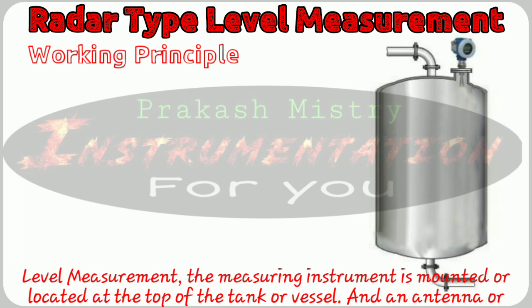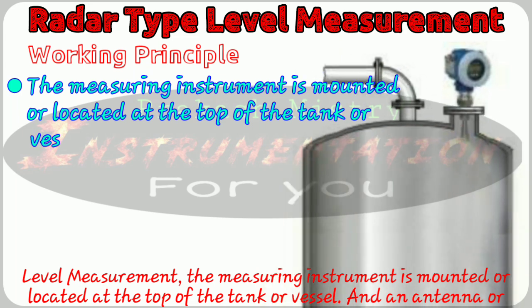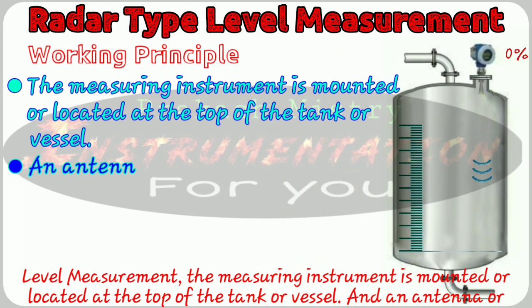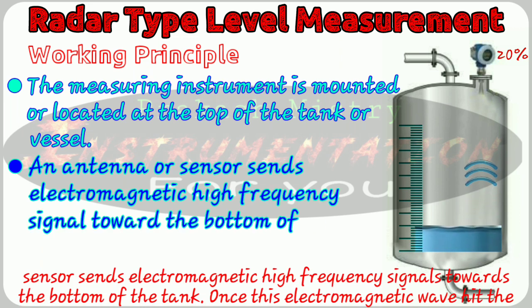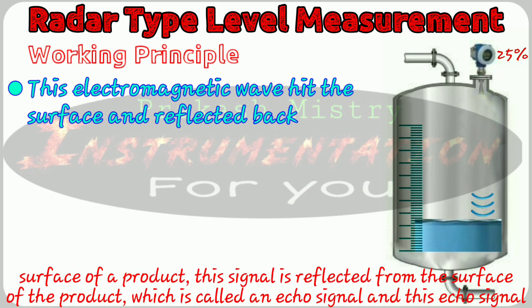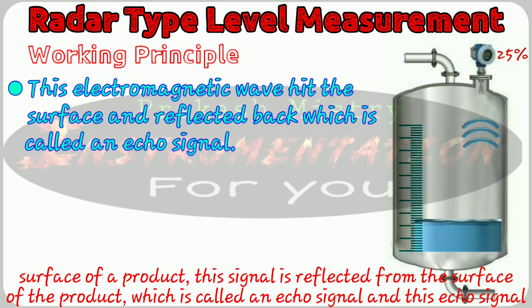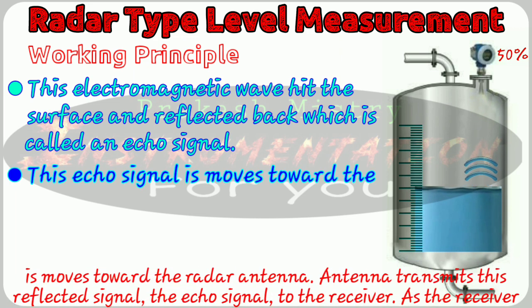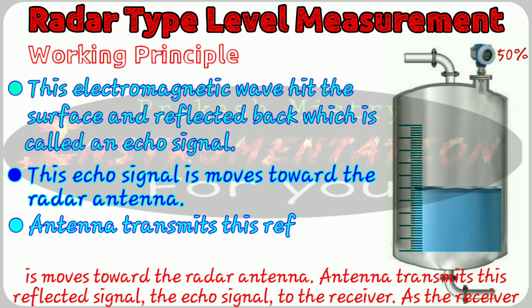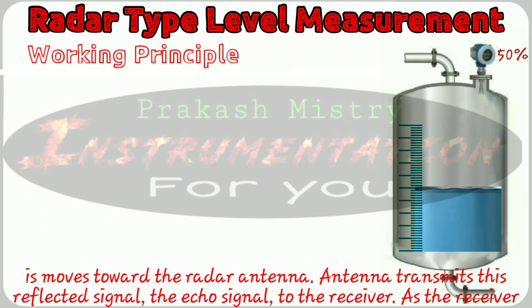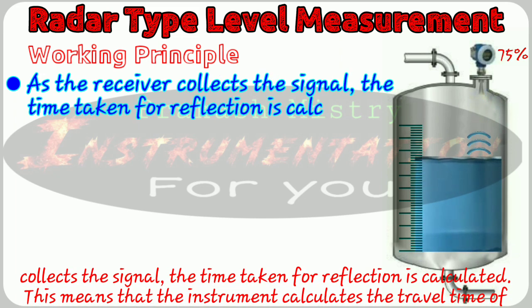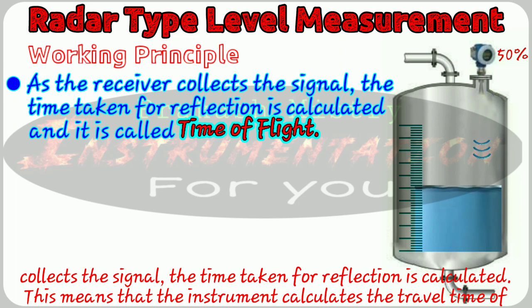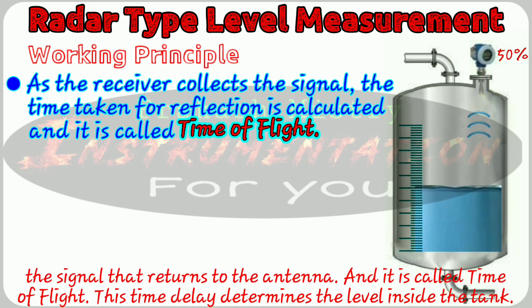In radar type level measurement, the measuring instrument is mounted at the top of the tank or vessel, and an antenna or sensor sends electromagnetic high frequency signals toward the bottom of the tank. Once these electromagnetic waves hit the surface of the product, the signal is reflected from the surface — called the echo signal — and this echo signal moves toward the radar antenna. The antenna transmits this reflected echo signal to the receiver. As the receiver collects the signal, the time taken for the reflection is calculated — this is called the time of flight.